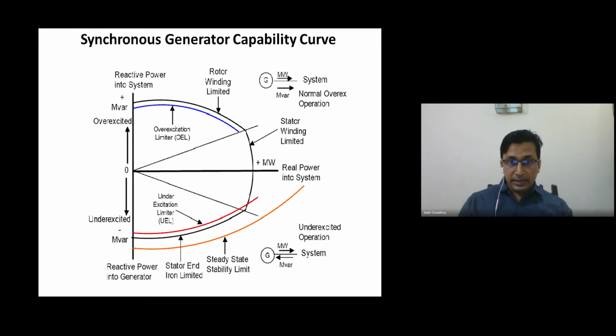So that shows how much excitation we can give a generator. That blue curve in the positive y-axis is the over excitation limit, and the red curve in the negative y-axis is the under excitation limit. We need to run the generator in between this.